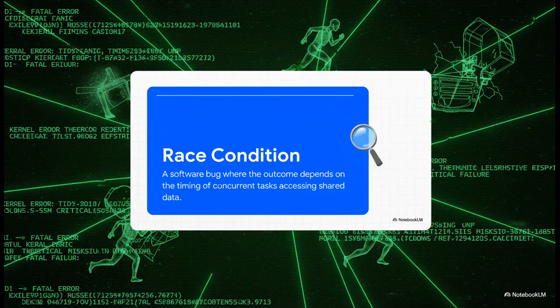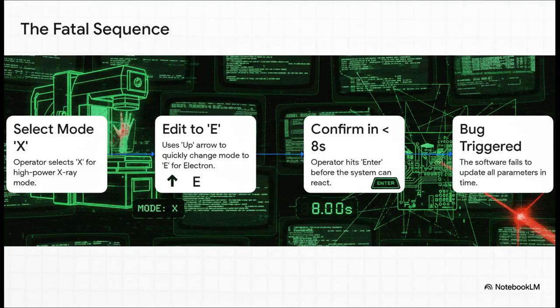The result all depends on which piece of code wins the race, which leads to totally unpredictable and, in this case, catastrophic behavior. Okay, so here is exactly what those fast typing operators were doing. They would select X for X-ray mode, then really quickly use the up arrow key to edit that entry to E for electron mode, and then hit Enter, all within about 8 seconds. This rapid-fire sequence is what triggered the race condition. One part of the software registered the command to fire the high-power X-ray beam, but the physical turntable, which was controlled by a slower part of the software, just didn't have enough time to move into the right position.